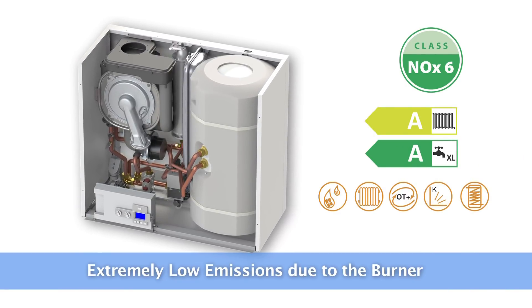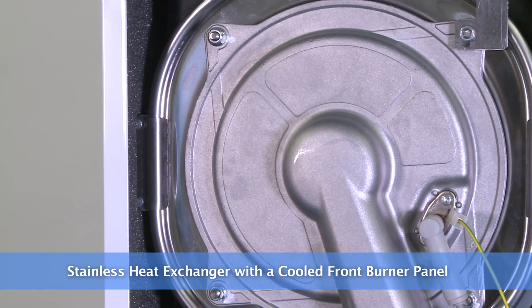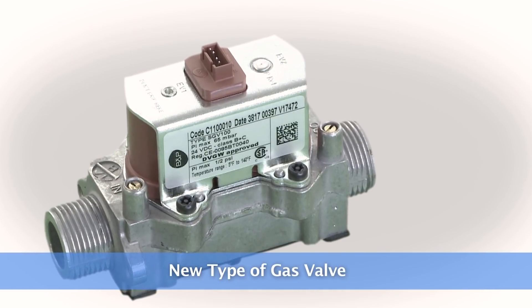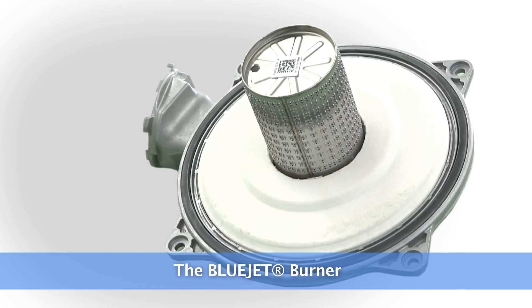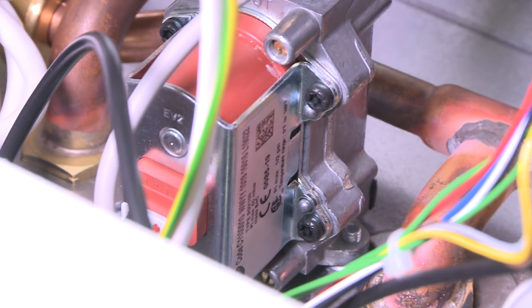Part of the boiler is the stainless heat exchanger with a cooled-front burner panel. A completely new type of gas valve optimizes the process of burning and consuming the gas, to prevent unnecessary energy losses. The gas valve then works with the blue jet type of burner to produce a high degree of modulation. This solution allows efficient burning at low rates of gas flow.